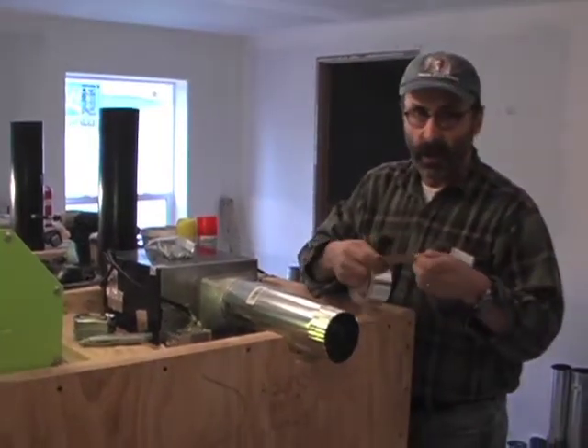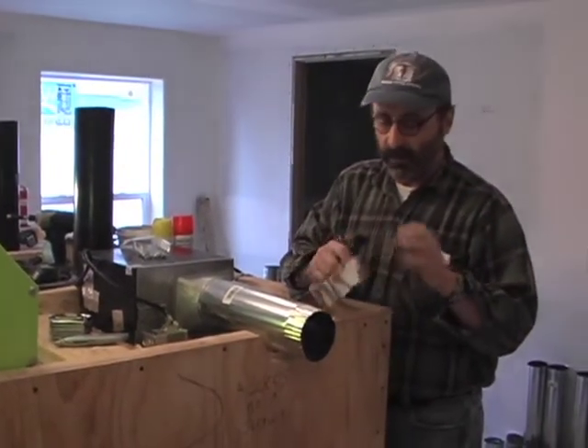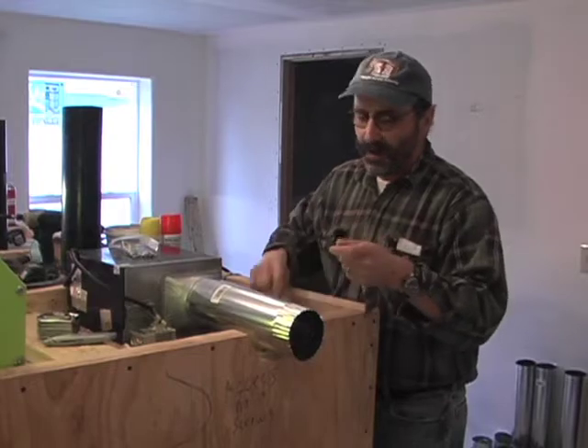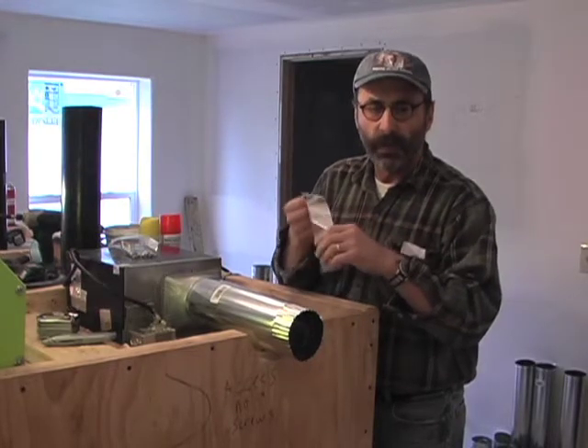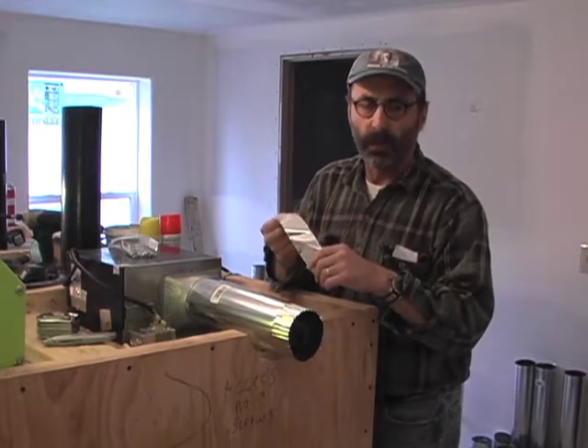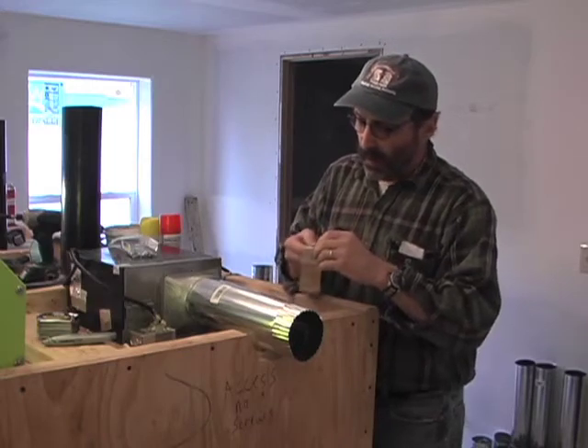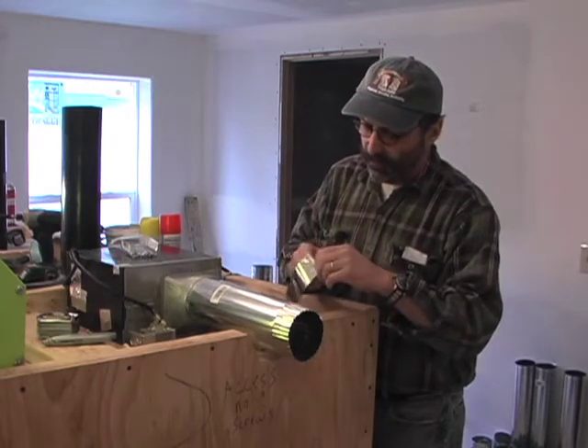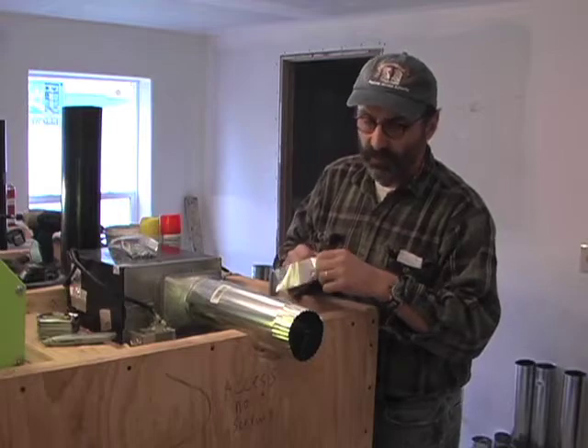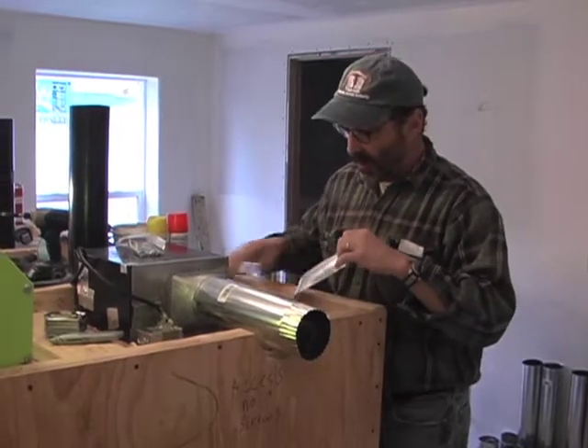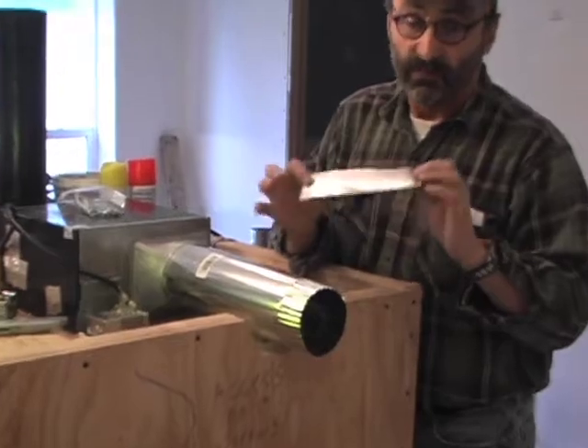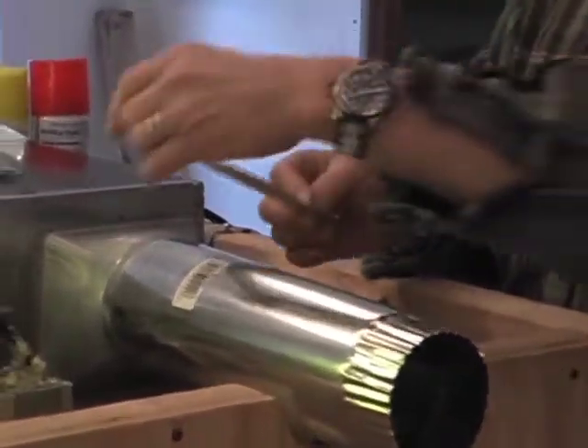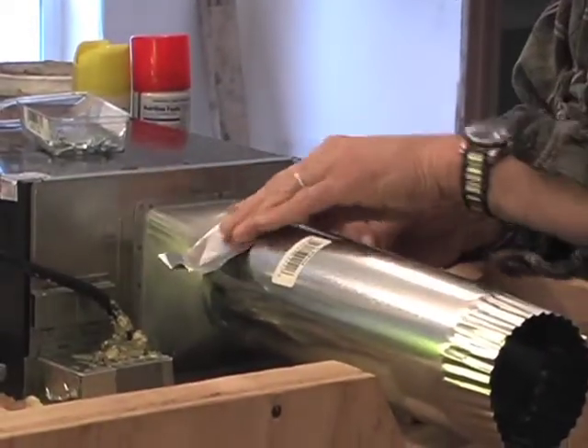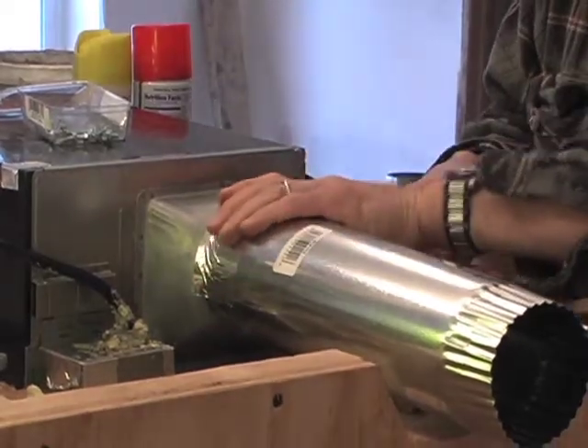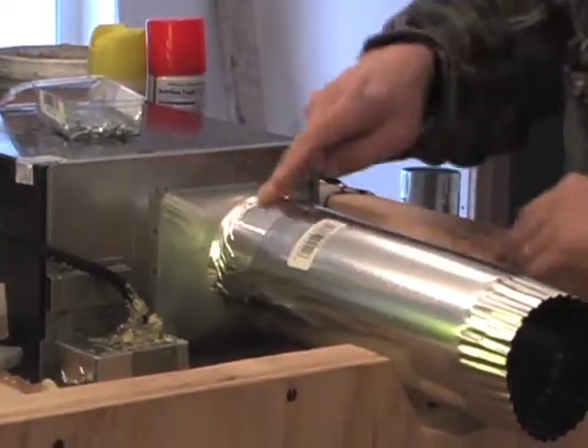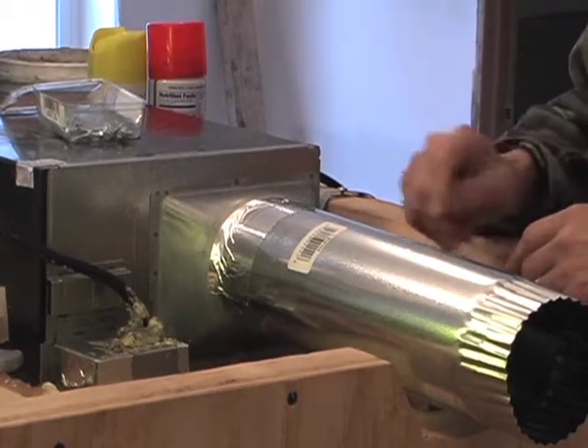Metal foil tape, ideally butyl-backed metal foil tape, would be a far better choice. My personal preference would be not to use metal foil tape. It would go to a latex-based mastic. If you do go with tape, it should be in a place where you have the ability to inspect it over time. Often the tape will perform super, other times the tape will not. We want to make sure we have enough of a spot here that we can get that tape on and make a good seal.